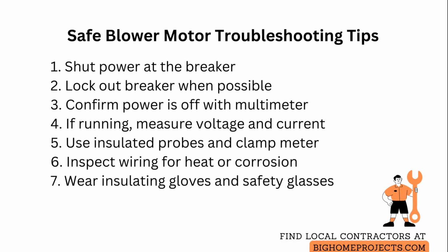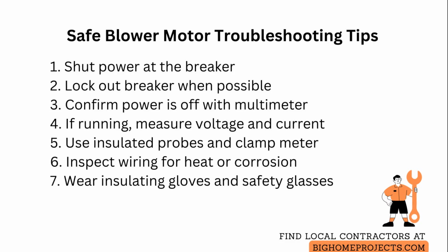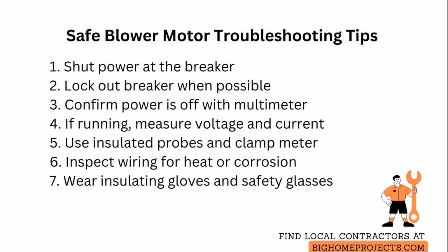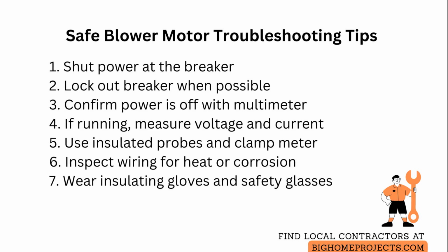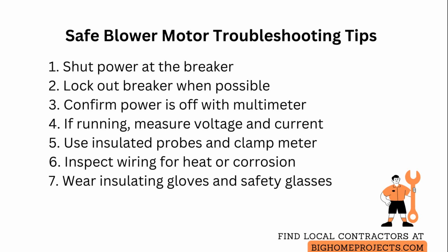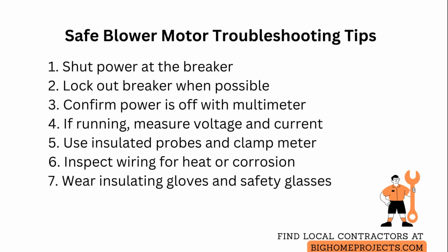Check motor bearings and fans by briefly powering and listening for unusual vibration or grinding, but only after physical guards are in place and you are clear of rotating parts. Use personal protective equipment such as safety glasses, insulating gloves rated for the system voltage, and arc flash protection when local procedure identifies a hazard.